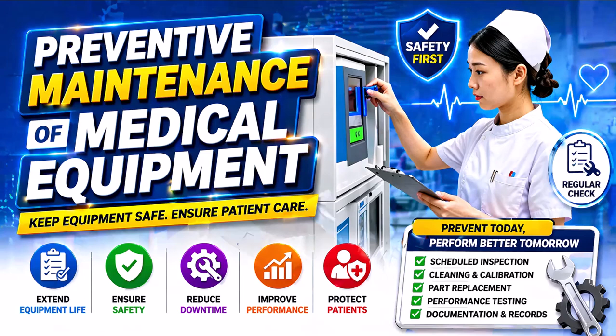Preventive maintenance activities usually follow a scheduled plan, which is based on manufacturer recommendations, hospital policies, and regulatory requirements. Some equipment requires monthly maintenance, while others may only need servicing every 6 months or once a year. Technicians must follow these schedules carefully and document all maintenance activities.